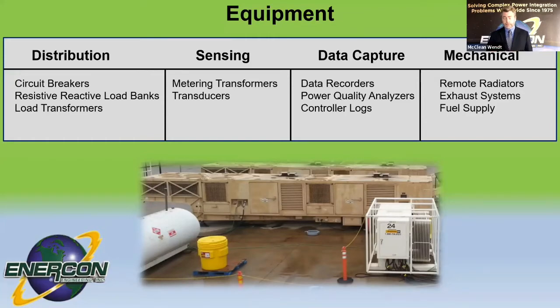The resistive and reactive load banks are used to simulate the loads that the power system is going to be designed to support. The reactive component of that creates the power factor, and those can be either inductive or capacitive. We typically use inductive, but have had times where we've run tests with capacitive, and we just need to rent the correct load bank if we do not have the right one on our lot. The load transformers will step down the voltage. Typically used for medium voltage, we'll step it down to 480, which is a typical supply for our load banks. But we have also had projects where we deal with various different unusual magnitudes that we need to get back down into the right range for our load banks.